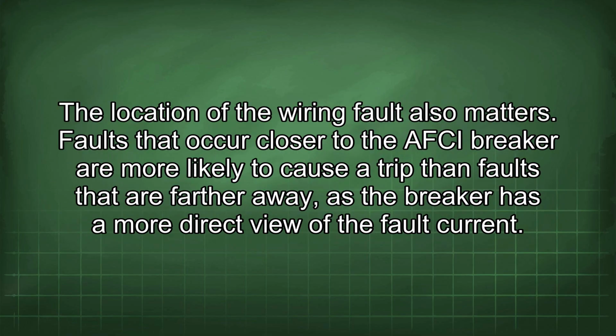The location of the wiring fault also matters. Faults that occur closer to the AFCI breaker are more likely to cause a trip than faults that are farther away, as the breaker has a more direct view of the fault current.